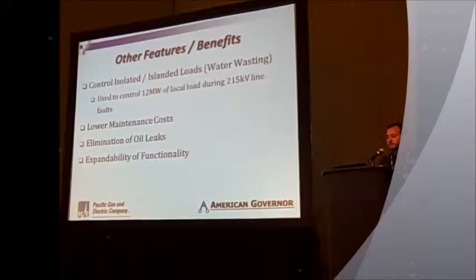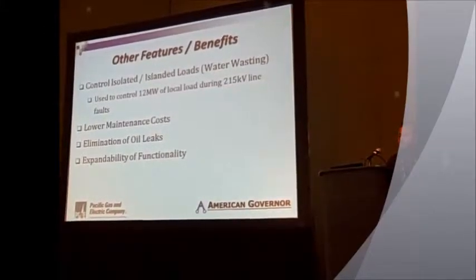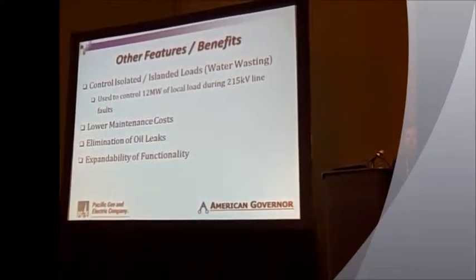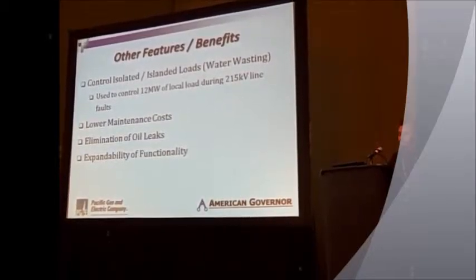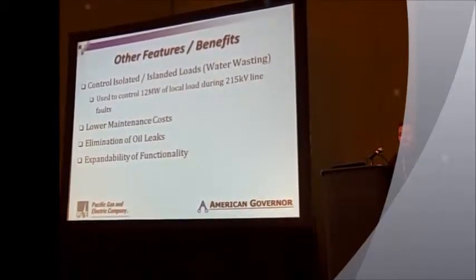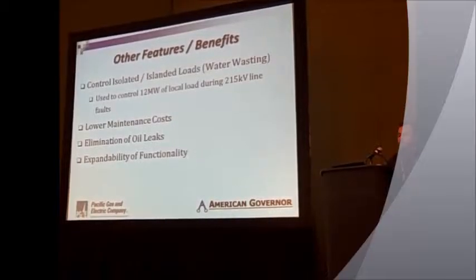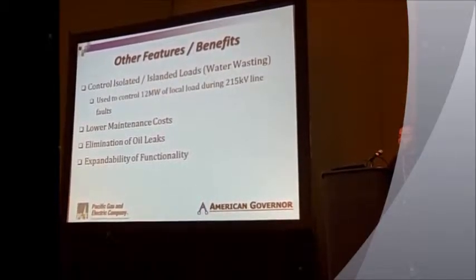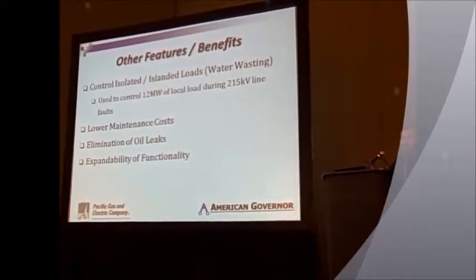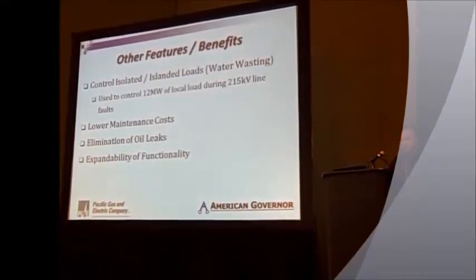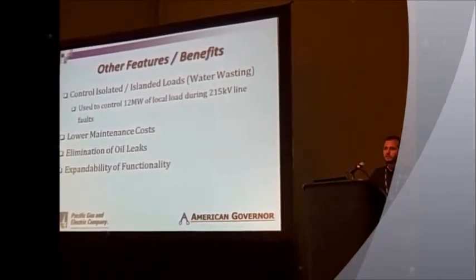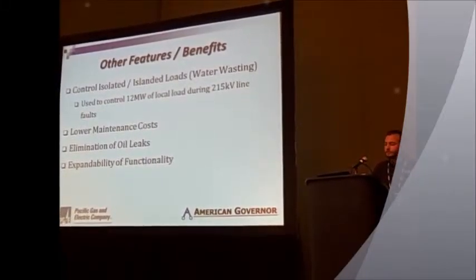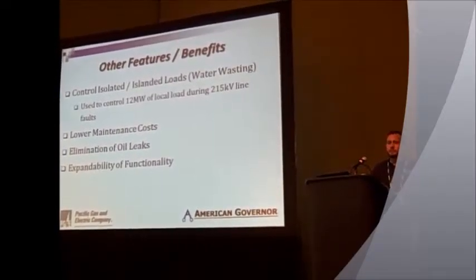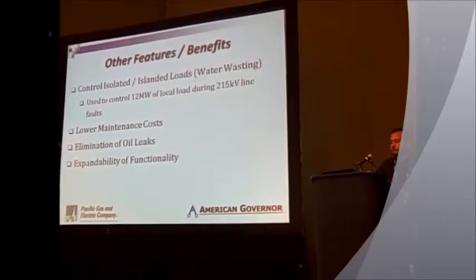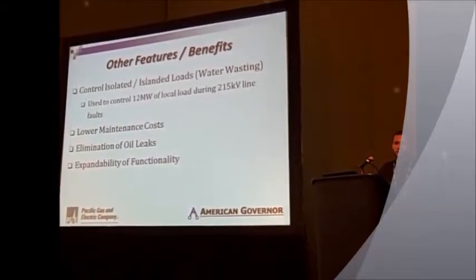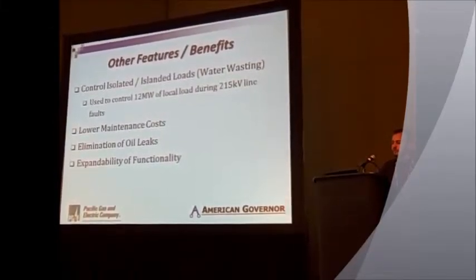So real quick, some of the other features that were obtained with the digital conversion: through the ability to independently control the deflectors and the needles, we can control isolated loads. There is the ability to control a roughly 12 megawatt load in the event of losing all 215 kV lines. That's through something called water wasting, where the needles are positioned roughly where they need to be for that 12 megawatt load, and the deflectors are the controlling mechanism. Deflectors, being much faster than needles, are much better suited to control speed.